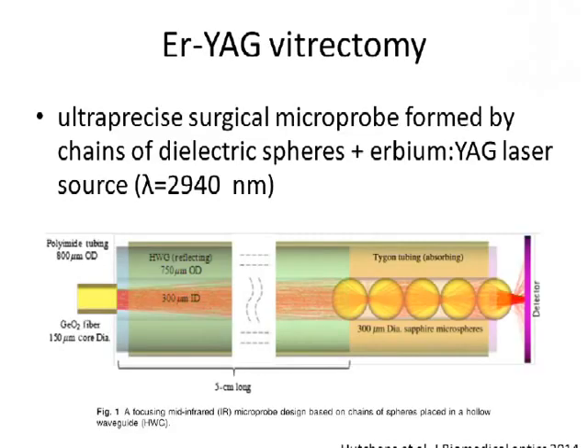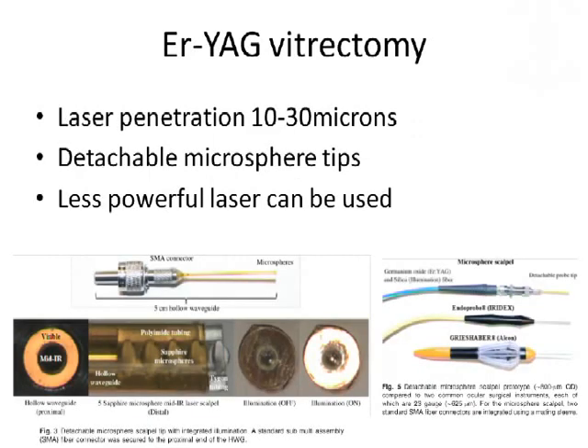Now, probably a couple of months back, there is a new interest. They have modified the probe by adding these microspheres here. These microspheres tend to focus the laser exactly at the tip, thereby decreasing the damage to the retinal tissue. So there is a prototype probe. The advantage is we can just remove this part of the probe and replace it. So the most expensive part, the fiber optic, we can retain, and only the tip can be replaced. There is a cut section here showing the size of the sapphire microsphere, and it also has inbuilt illumination. So you can see and also cut using these probes.